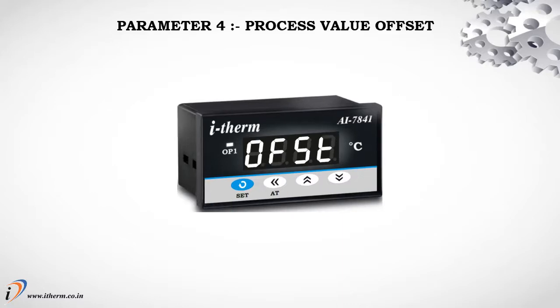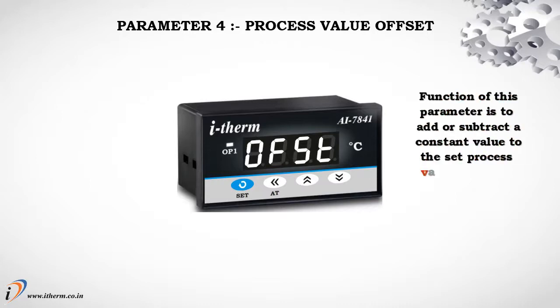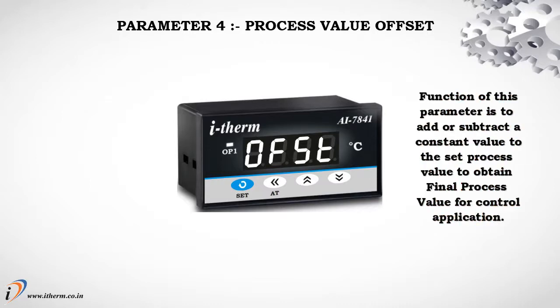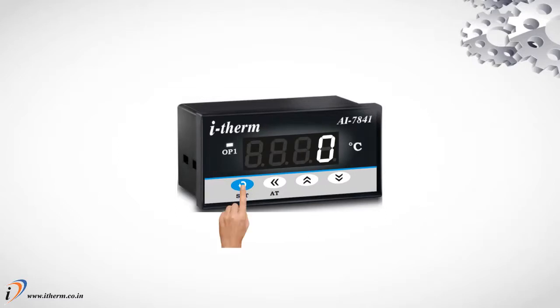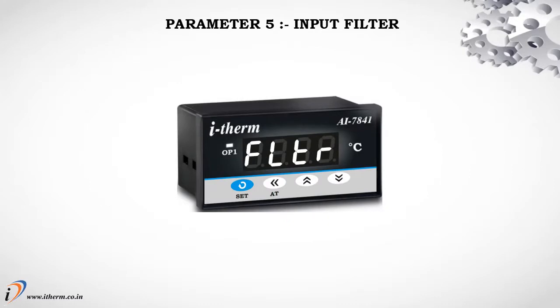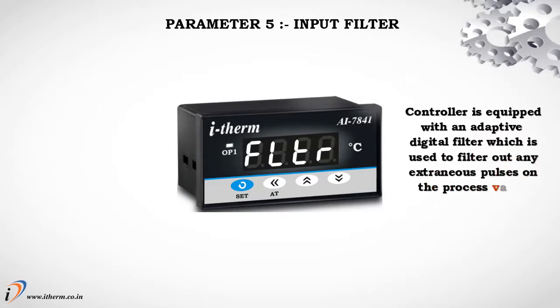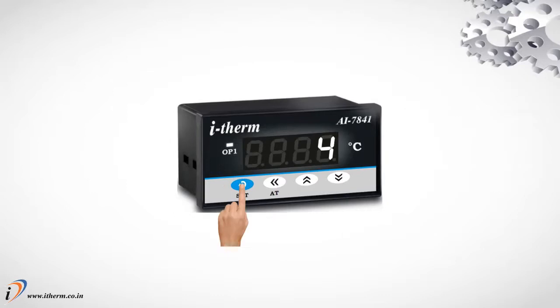Parameter 4, Process value offset. Function of this parameter is to add or subtract a constant value to the set process value to obtain final process value for control application. Default process offset value is 0. Parameter 5, Input filter. Controller is equipped with an adaptive digital filter which is used to filter out any extraneous pulses on the process value. Default input filter value is 4.